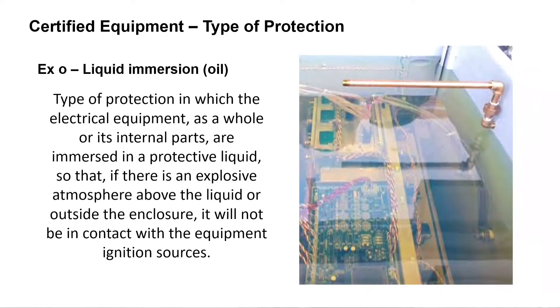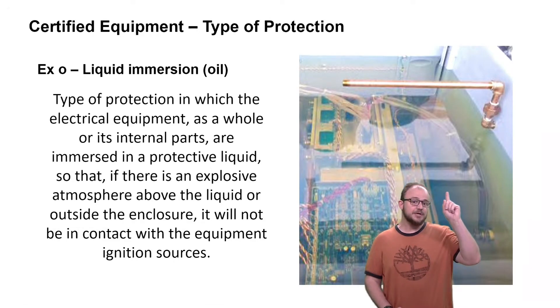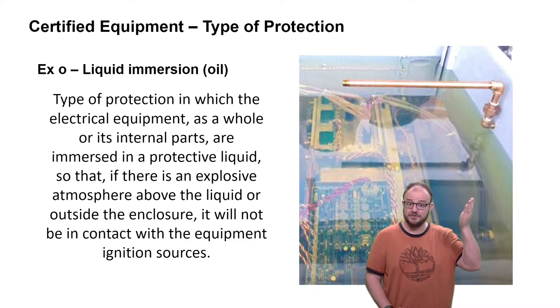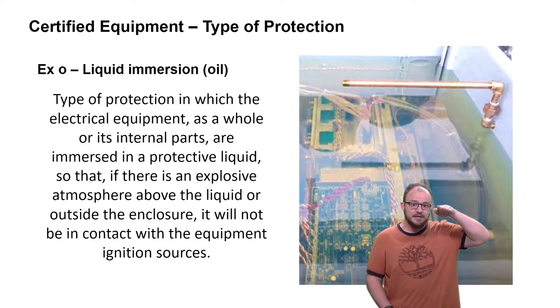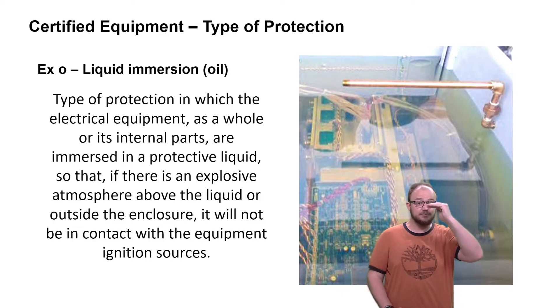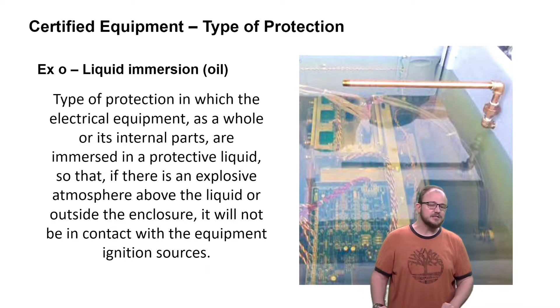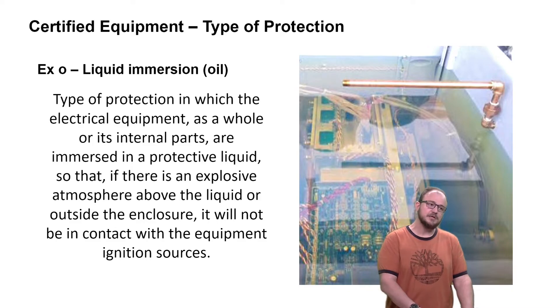We also have liquid immersion. In past years it was oil immersion — that's why the code is Ex o. But during the last couple of years, new types of liquid were invented for this purpose, so they are now called liquid immersion. However, because it uses a liquid, if you put this equipment on a ship where there is movement and changes in sea level, it can lose the protection of the liquid level. So it's not a very good option for ships and other places where there is movement.